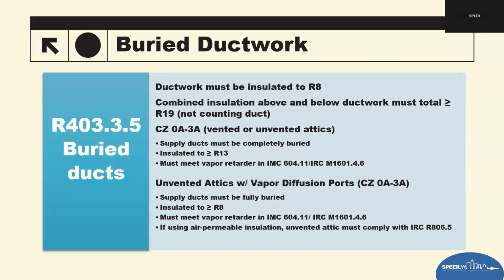Buried ducts are the next thing I was going to go through, though we may not see a lot of this happening in Texas. First, all buried ducts must be insulated to an R8. This is if you're burying the ducts. We know that if it's completely inside of a conditioned space, technically it doesn't have to be insulated, but this is burying the ducts in insulation. So I'll move to the next. Basically, in climate zones 0A through 3A, in vented and unvented attics, in hot, humid climates like Texas, supply ducts must now be completely buried inside the insulation, no partial coverage. These ducts must be insulated to at least R13. There's a major change from past versions.